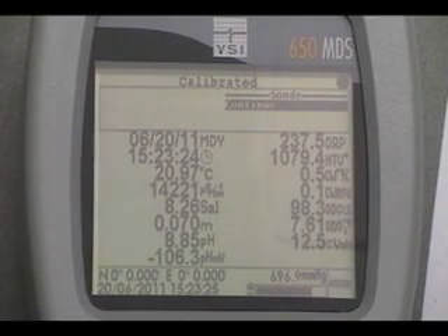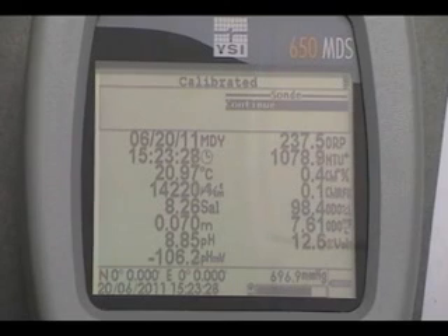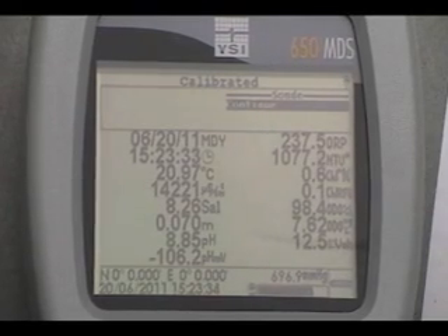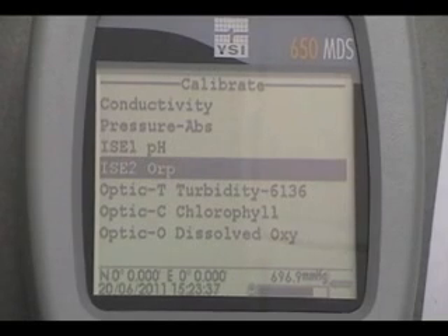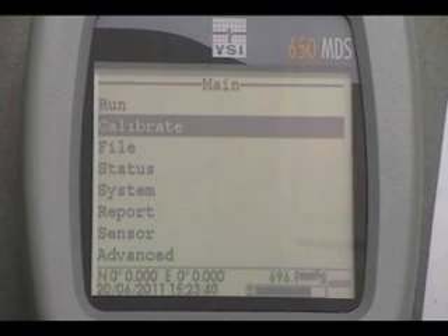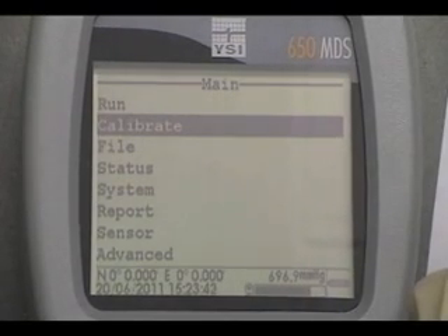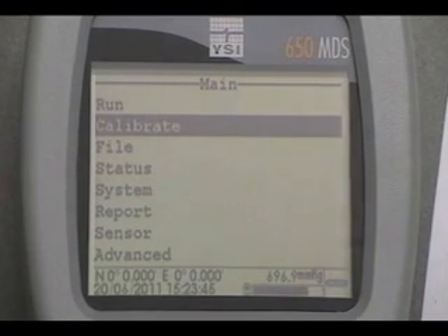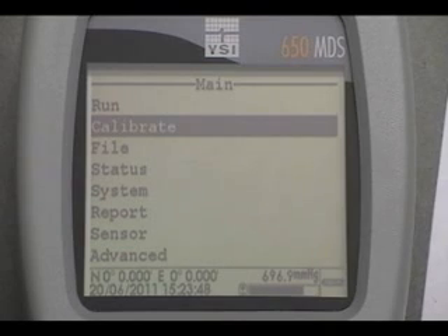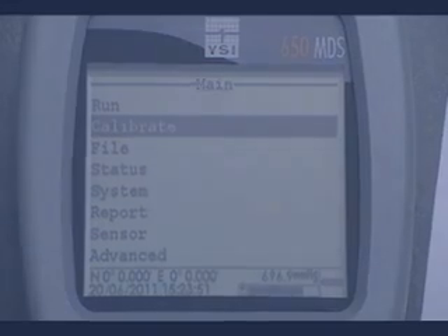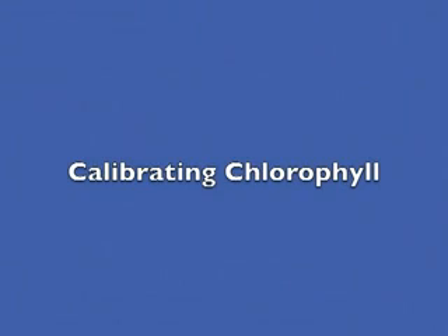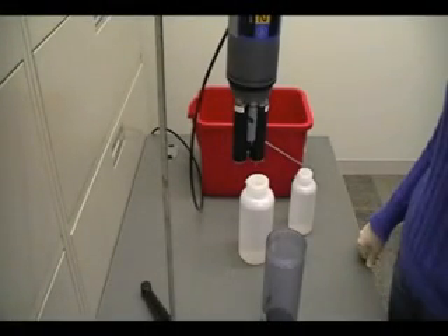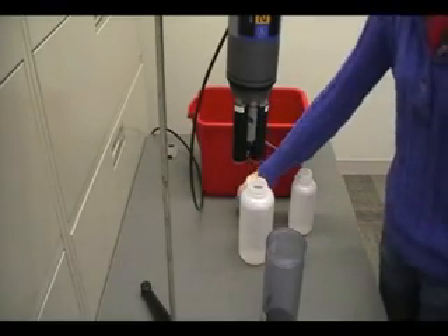and record the post-calibration ORP value in millivolts on the calibration worksheet. Step 9. Press Enter to continue and Escape to return to the main menu. Step 10. Reorient the sonde, empty the calibration cup, and rinse the sensors and cup with deionized water. Calibration of ORP is now complete. Chlorophyll calibration. Step 1. Ensure that the sensors and cup have been rinsed thoroughly with DI water. Submerge the chlorophyll sensor in deionized water.